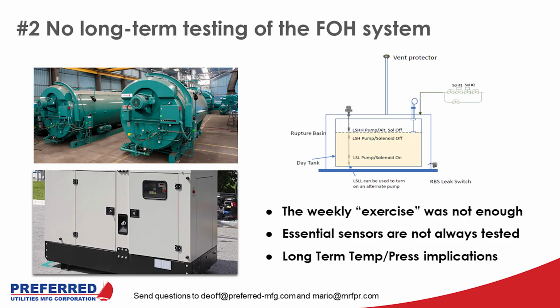Some end users had that occur. Ideally, you would have a return pump that would send the fuel using the return line back to the main tank. That would remove the warm fuel and would replenish the day tank with cooler fuel. Also, pressure swings. When you have boilers and gensets that are all coming in and out and they have different flow requirements, that could cause some pressure swings. We had multiple end users that started using pressure regulators or replacing pressure regulators that perhaps were not operating properly. And once that was implemented, that really helped out with the pressure swings.